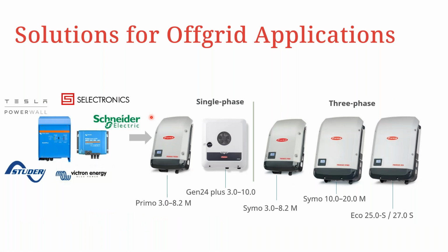So let's now talk about the configuration of an AC coupled setup. So for off-grid applications where microgrid solutions through AC coupling would be quite beneficial, but in other setups also, like we said, in a grid setup where the grid is not stable or where you want to give backup for the grid, you could use quite a number of battery inverters.